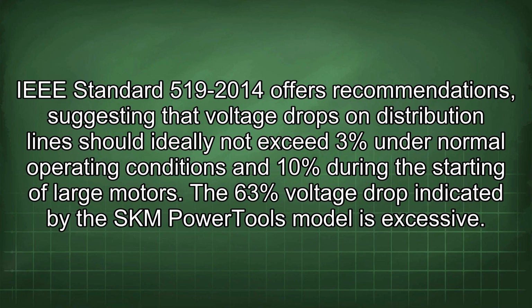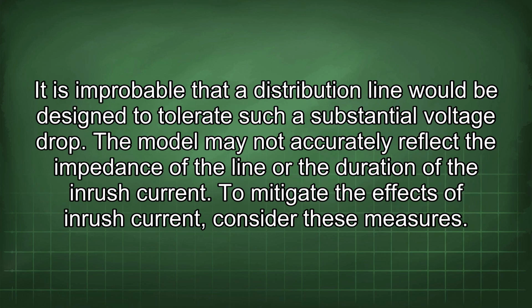IEEE Standard 519-2014 offers recommendations suggesting that voltage drops on distribution lines should ideally not exceed 3% under normal operating conditions and 10% during the starting of large motors. The 63% voltage drop indicated by the SKM Power Tools model is excessive. It is improbable that a distribution line would be designed to tolerate such a substantial voltage drop. The model may not accurately reflect the impedance of the line or the duration of the inrush current.